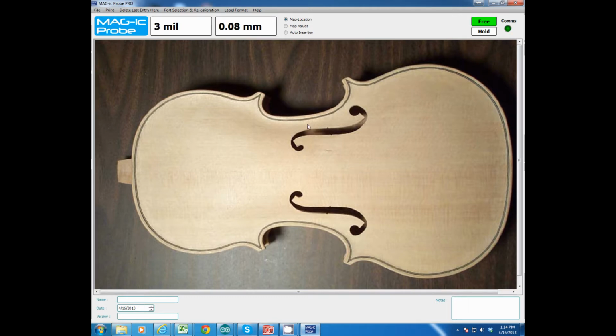So I'm now ready to do some measurements on the screen. You'll see that when I move the magnet on the probe, the readings are changing. I'll get to a stable measurement here. So there's a measurement that I'm measuring right now: 2.92 millimeters, 115 mils. This is obviously the metric reading, and mils is thousandths of an inch, being 115 thousandths of an inch right now.